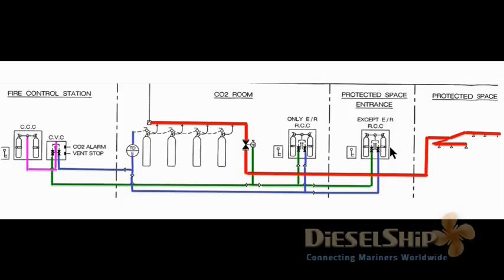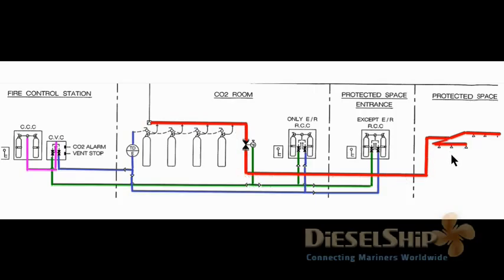When operating from the engine room entrance, remember that somebody has to go to the fire station or emergency station to shut quick-closing valves, and emergency stops of blowers, pumps, and dampers must all be done — or all arrangements must be available just outside the engine room. After confirming everything is clear and mustering order from the captain, the chief engineer operates the two valves. Opening the pilot bottle gives a pressure indication. The green line goes through a check valve and opens the main distribution valve; the blue line goes through a non-return valve and time delay unit to the CO2 bottles in the CO2 room. The CO2 is released and through the distribution valve goes to the engine room. This is how the CO2 system is operated.